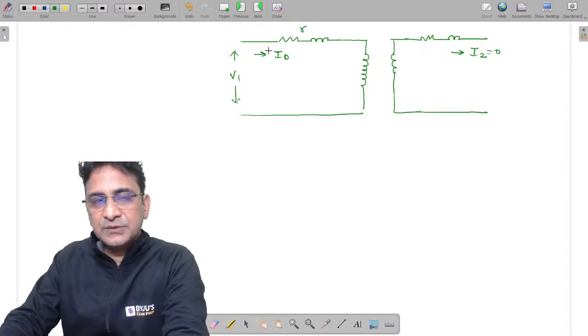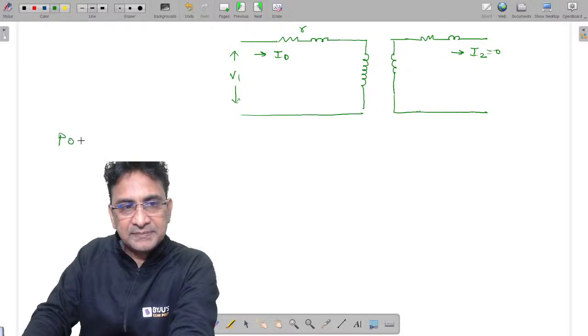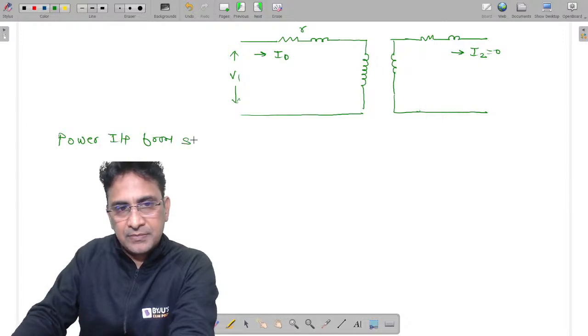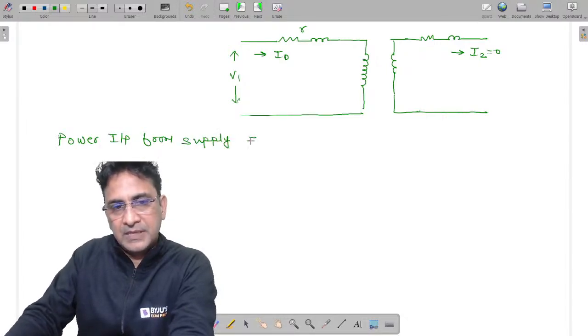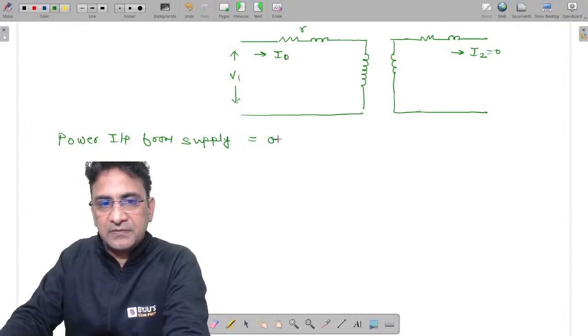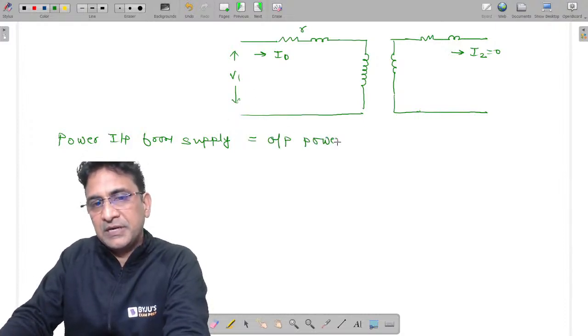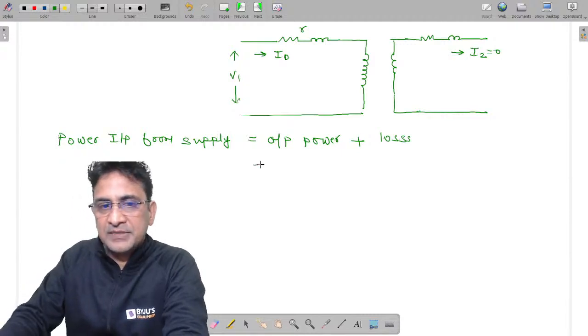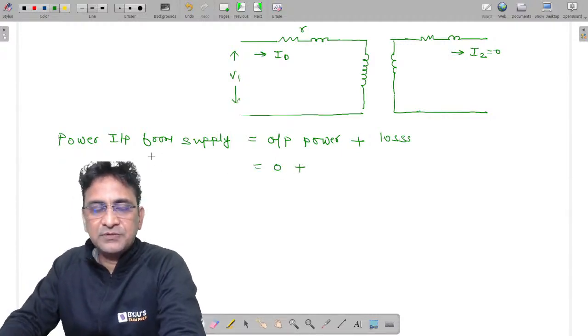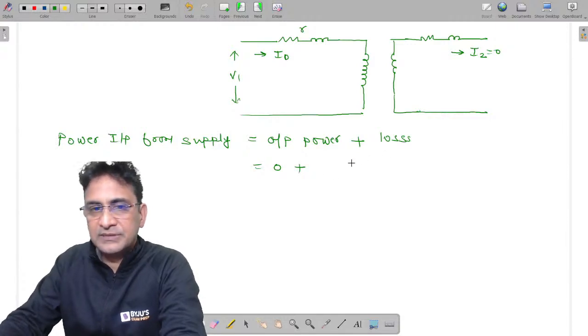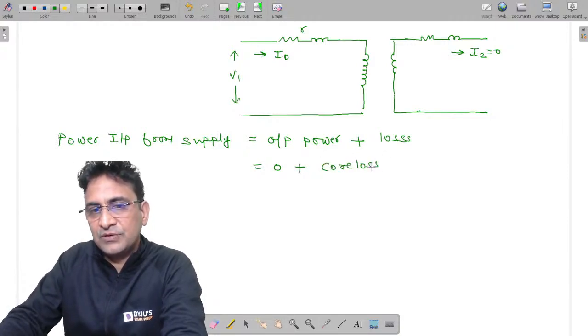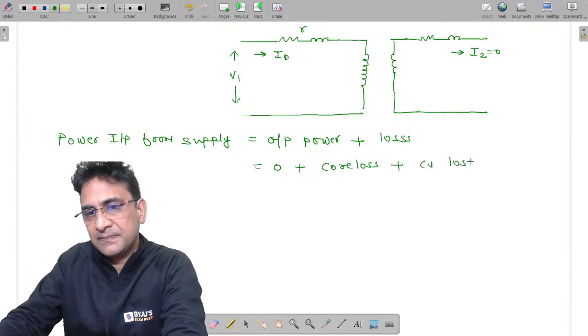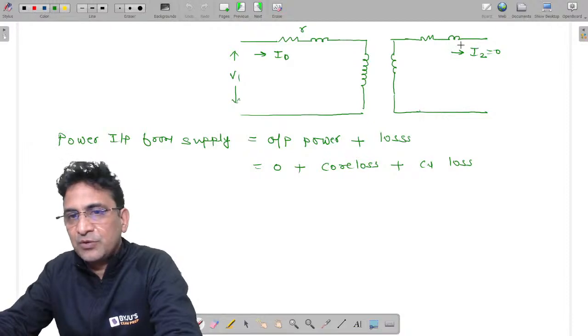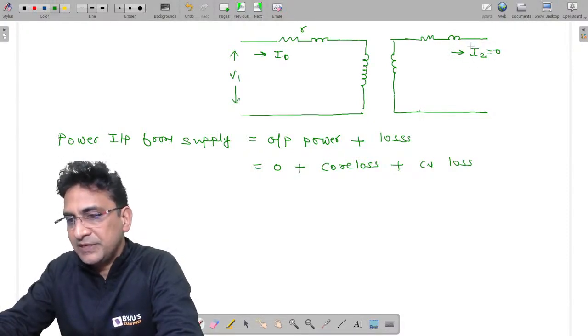The resistance is neglected. So what is the power that we are drawing? The power input from supply. If you are giving the power to a transformer, it will either be available at the output or it would be converted into the losses. Since no load is connected here, the output power is equivalent to 0. So whatever power you are giving to the transformer, it is converting into the losses. So we have two types of losses. One is called the core loss and the second is called the copper loss. No doubt, no current is flowing in the secondary side, so the secondary side copper loss is equivalent to 0.